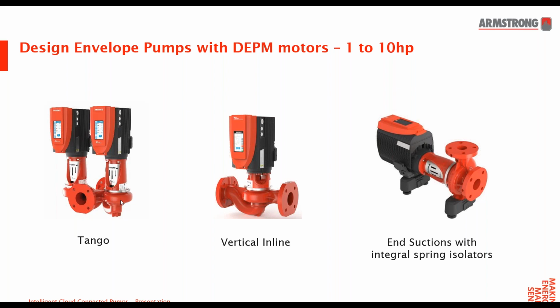But you're running it at 3,600 RPMs, right? A lot of times when we run into voltage issues, it just derates the output of the pump. Is that something you could make up on the fly if it's only running at 20% load? It could just increase the pressure at the lower voltage? No, it's not the voltage that dictates the speed. It's the frequency. Right. If it's a lower voltage, it would probably cause you to lose some RPMs, typically. Okay. But there would be a trigger to let you know that something was off there.